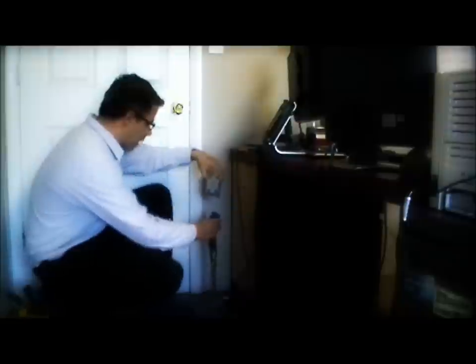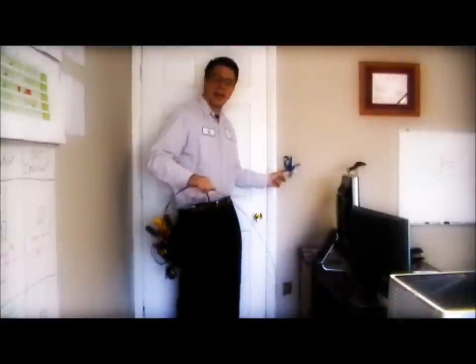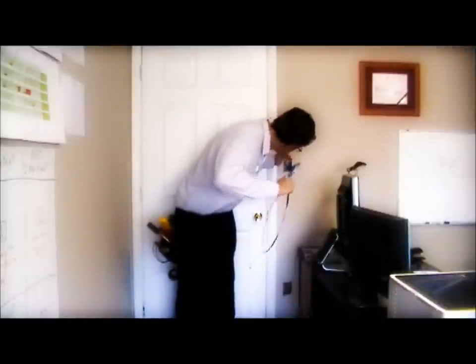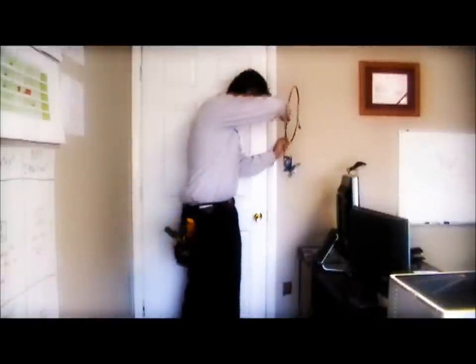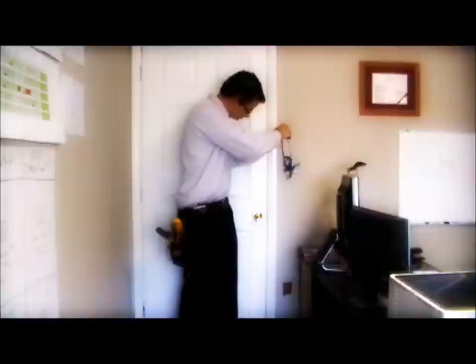This is an old work electrician's box. I'm going to use this box to install the new outlet. To find the height we're going to use an electrician's hammer. We're going to put it there, press the box on top, and trace out a pencil line. To get a wire from this box to this box to feed the outlet, I'm going to use this fish. It simply slips in the hole in the back of the box, drop it down there until it comes out the bottom. I'm going to reach in here and see if I can find it. There you go.